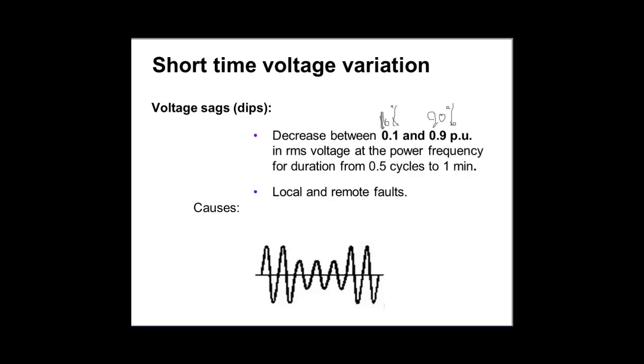So if temporarily, very, very quickly, what do you mean by very, very quickly? This is it: between 0.5 cycle and 1 minute. You understand the meaning of 0.5 cycle. In the UK, frequency is 50 Hertz. 1 divided by 50 makes 20 milliseconds. That's 1 cycle. Half the cycle means half the 20 milliseconds, which is 10 milliseconds. This is what we understand. 10 milliseconds, 20, 30, 40, something, okay?